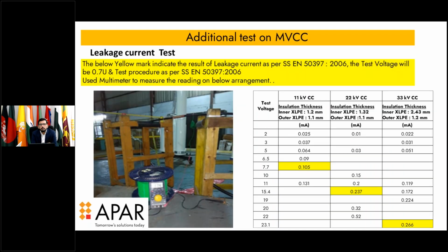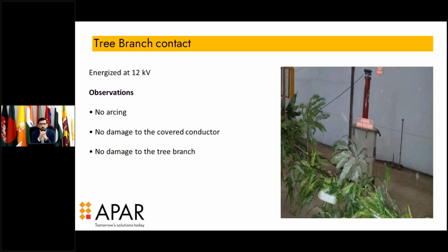In addition to this, we have conducted a lot of tests in our factory, because we already have our factory NABL accredited. We keep on doing a lot of innovative research and see the results on the covered conductors. You can see how the insulation thickness and leakage current can be measured at different voltages: 11 kV, 22 kV, 33 kV. We also do some testing to energize the 12 kV system with tree contacts. What happened when we did that? No arcing, no damage to the conductor, no damage to the tree branches. This is one of the positive ends of this technology.